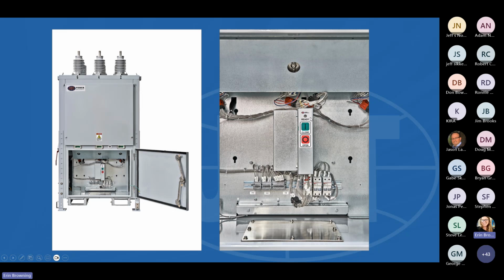And this ready light illuminates blue. So when that ready light is blue, that tells the operator the breaker is ready to go. There's sufficient voltage in the capacitor to drive the actuators open or closed, and the status of the breaker is healthy, all the poles are aligned, everything is kosher and good to go. When that light is blinking, it blinks at different speeds and different frequencies. It's almost Morse code looking. Depending on if the capacitor is charging, it blinks at a certain rate. If there's an error or an issue with the board, it blinks at a different rate. That is basically the first level troubleshooting mechanism for our customers, depending on the rate that the light is flashing.